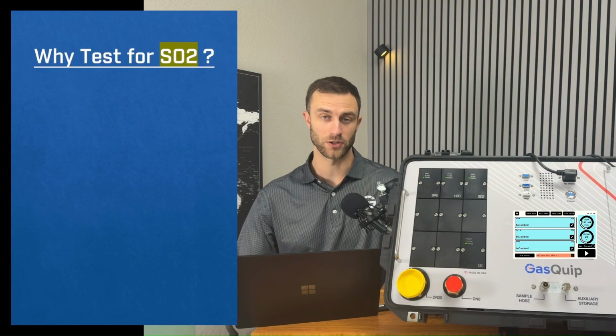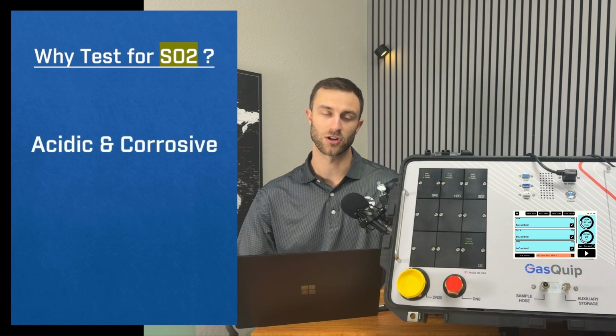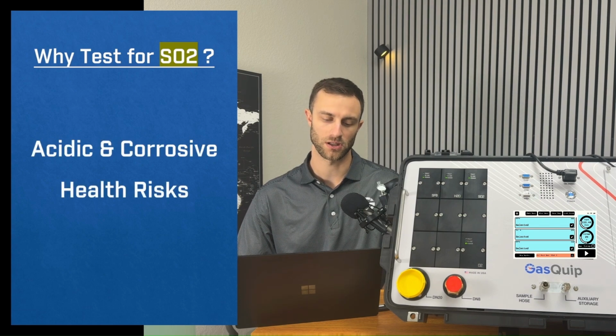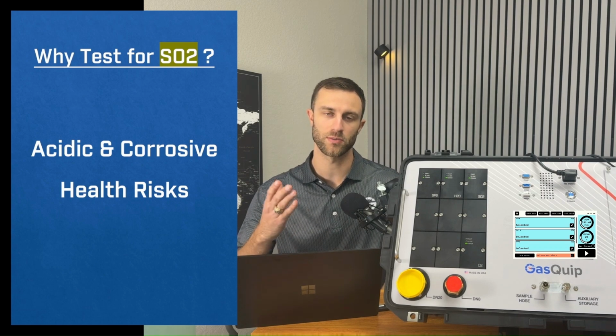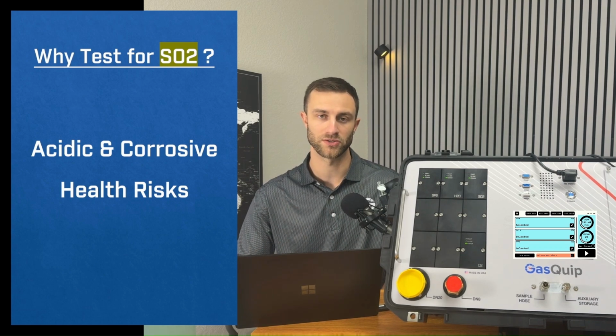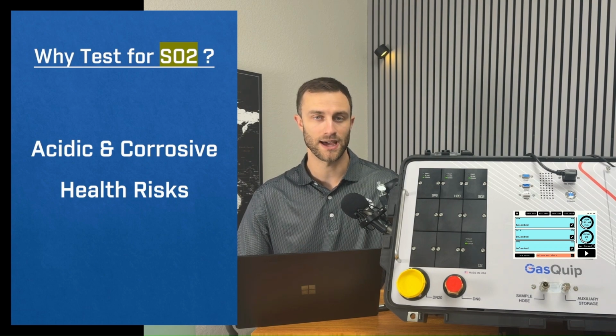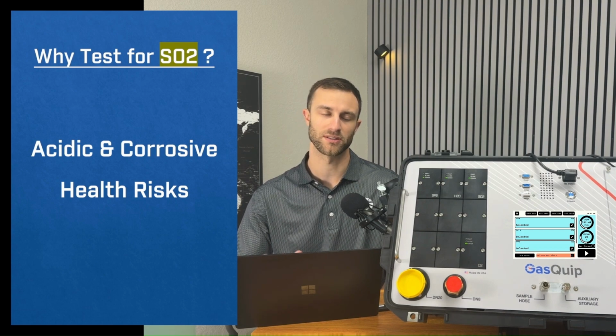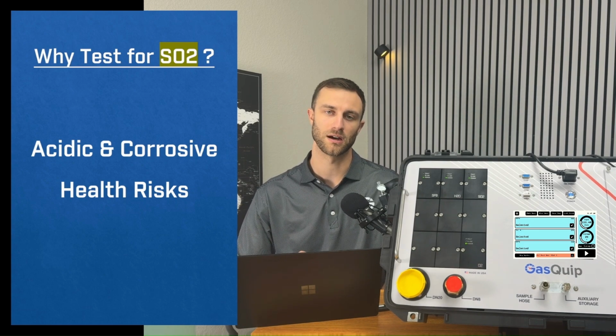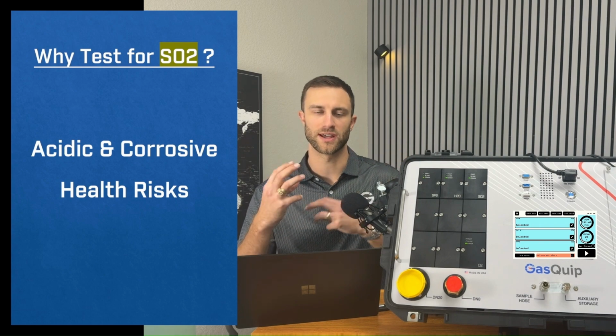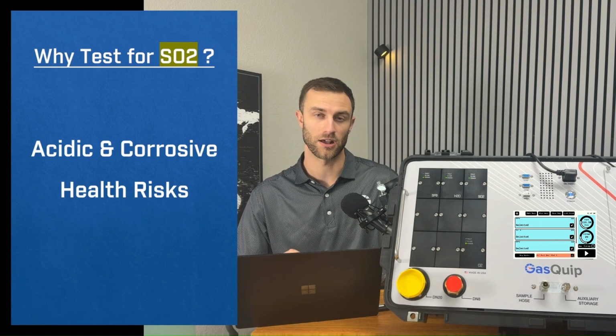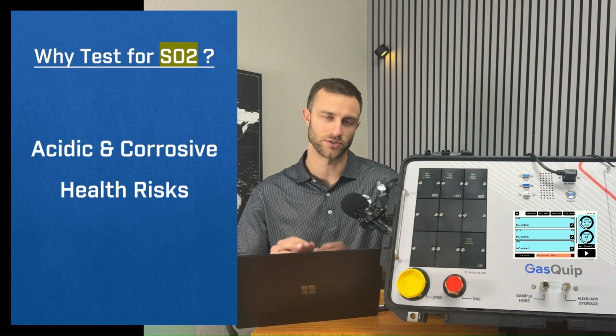Why do we test for SO2 or sulfur dioxide? Well, again, there's two main reasons to this. One is that it is very acidic and corrosive to the equipment that it is installed in, and also there is a lot of health risks to the operators. If an equipment does have measured amounts of SO2 inside of it, it also likely has other harmful acids and other compounds that are produced by the stuff that we talked about earlier with the high energy heat and H2O and SF6. SO2 is more of just a leading indicator that there is a lot of arc byproducts present, and it'll cause issues for the equipment and also the operators.